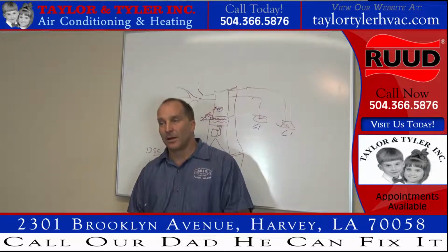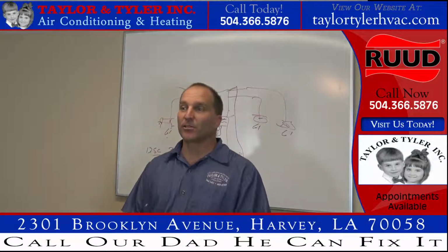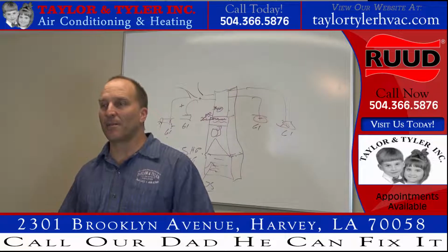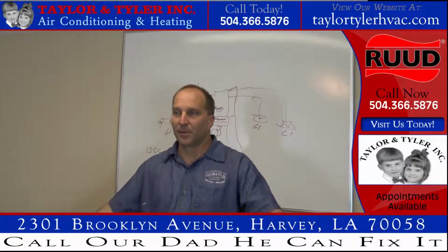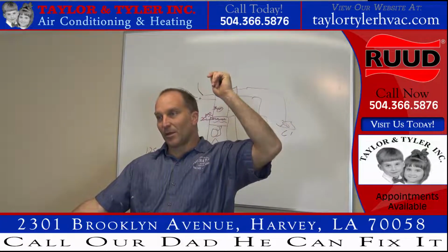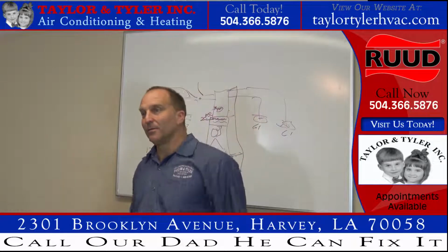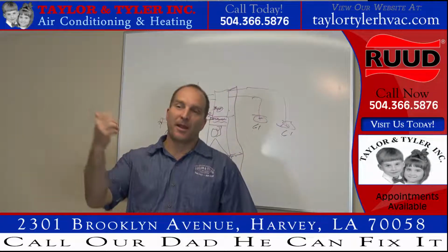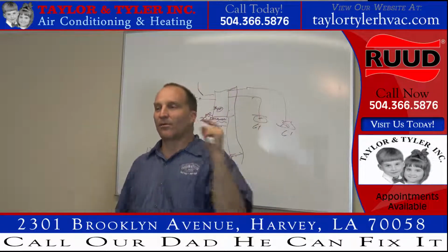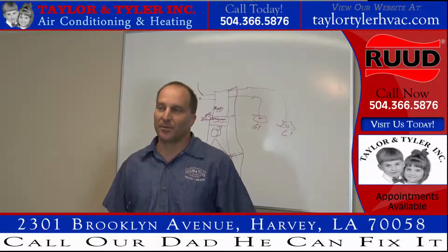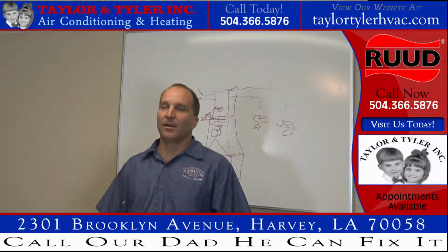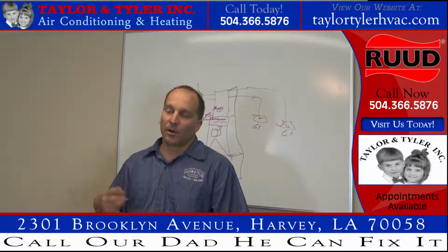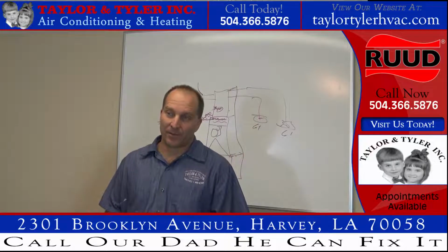So now I check pressures, head pressure, suction pressure, superheat, subcooling, all perfect. Delta T, 12, 14 degrees. I said, I know what's wrong. Open the system up, check the amperage. Sure enough, I got one 5 kW heating system running at the same time the air conditioner's running. Been running like that for a year. 2 to 3 other technicians, maybe one guy kept going back over there.